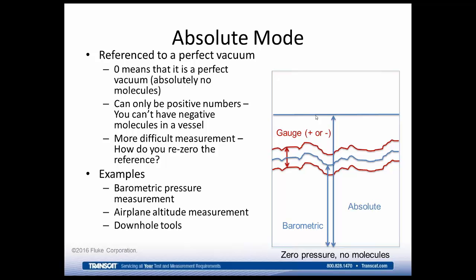That means that you need that other device. And so a lot of times, instead of zeroing it as a routine process, it gets zeroed as part of the calibration process once a year or so, 6 months, a year, whatever the calibration interval is. And so you've got to include that zero drift in the overall accuracy of the instrument.